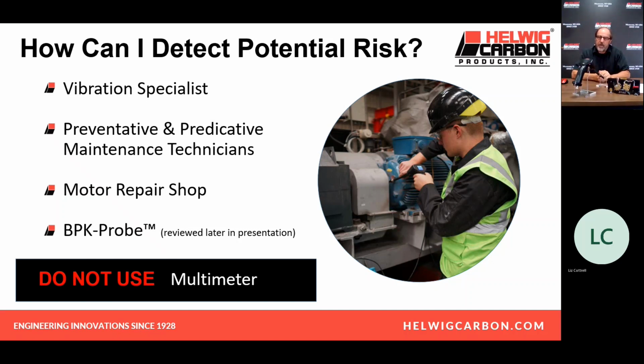So what do we got to do? We have to get on that motor shaft with an instrument that can detect voltage discharge. That's what this little device is here. You simply place it against the motor shaft, pull and hold a test trigger on here, and within moments you will see the risk to your motor, if there's one at all, and what that risk is. Okay, and then we record and store all that information. We do all that stuff.